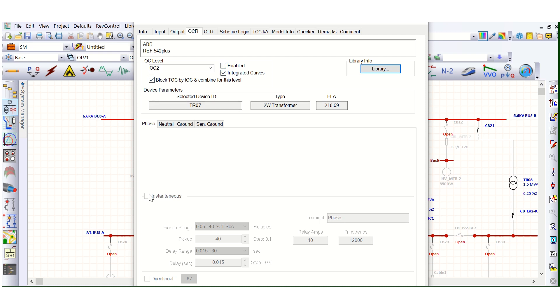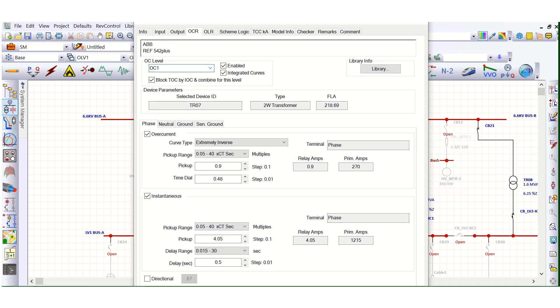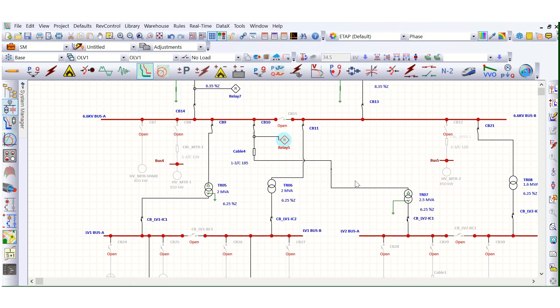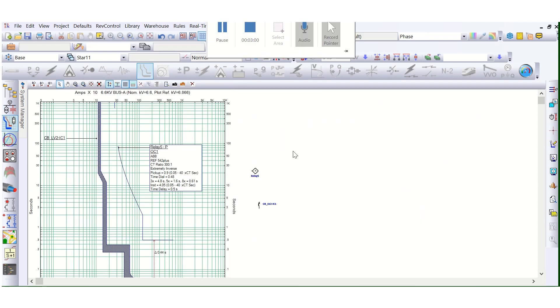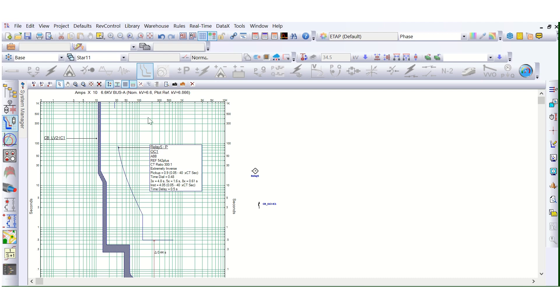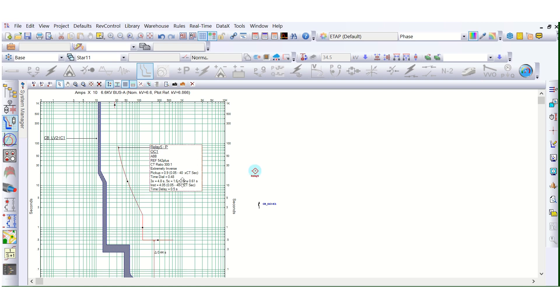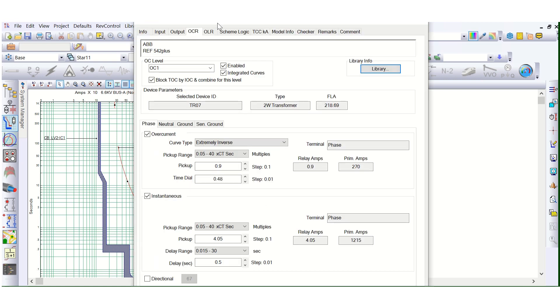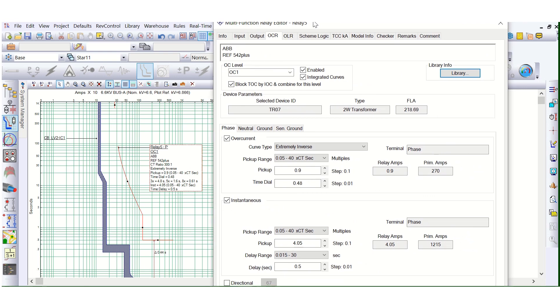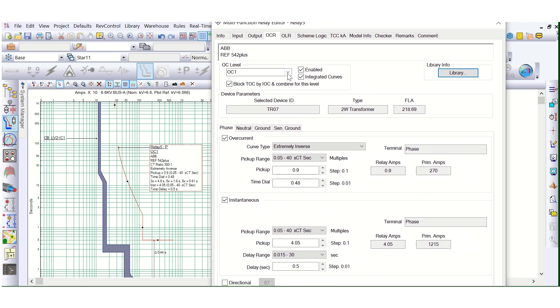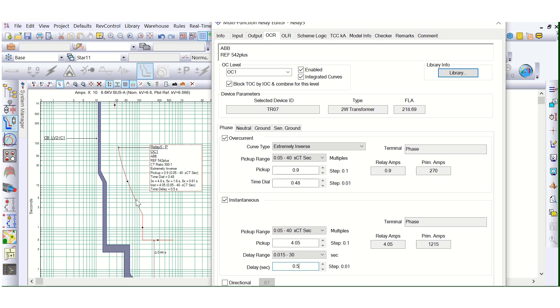Before enabling this OC2 level, let's go to OC1 and let's go to the TCC curve for better understanding. Here in this TCC curve, as you can see here, if we go, this is OC1, 51 is enabled, 50 also enabled, but this is not instantaneous basically, this is short time delay, 500 millisecond intentional delay I am giving. So this curve will look like this. This is 51 and this is 50.